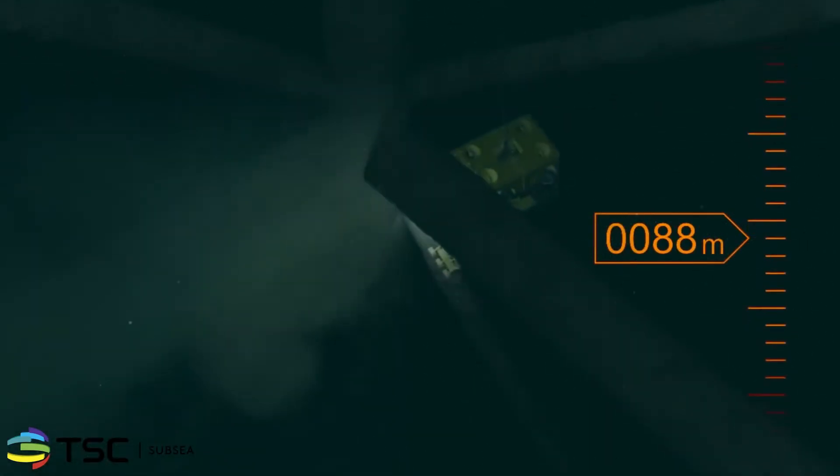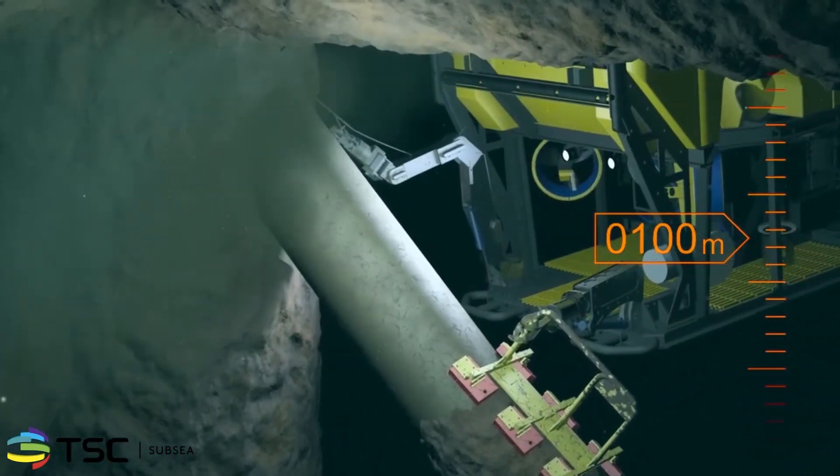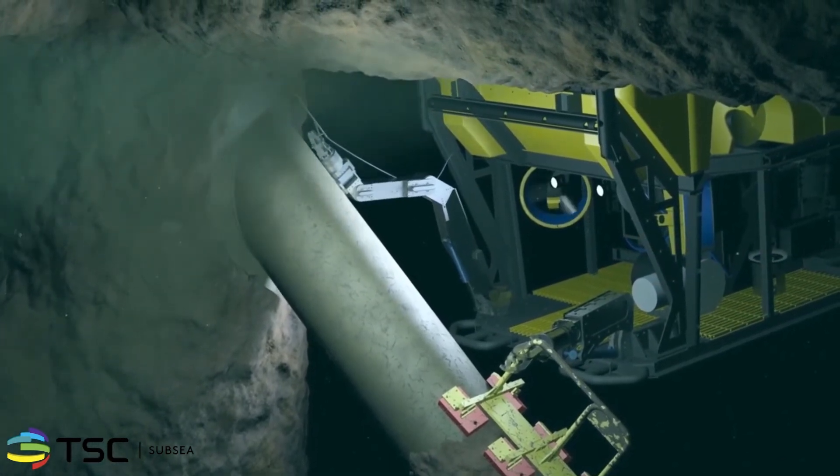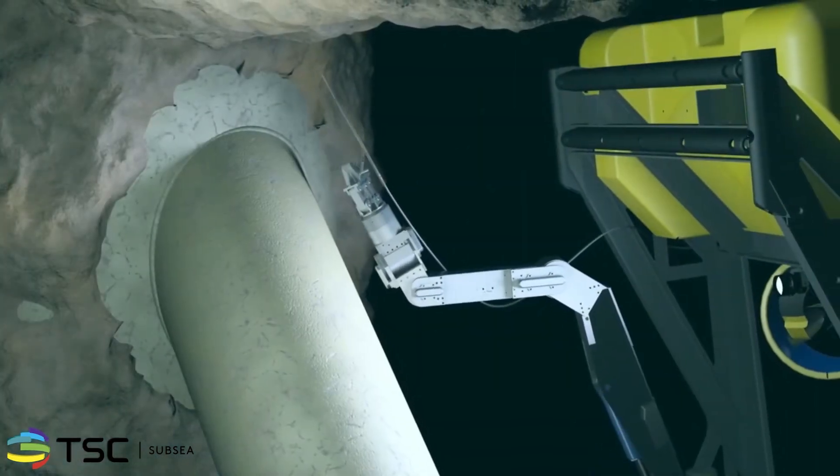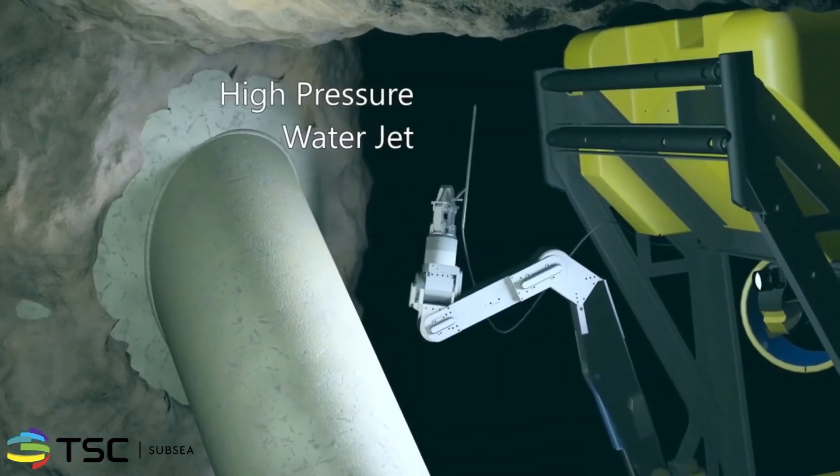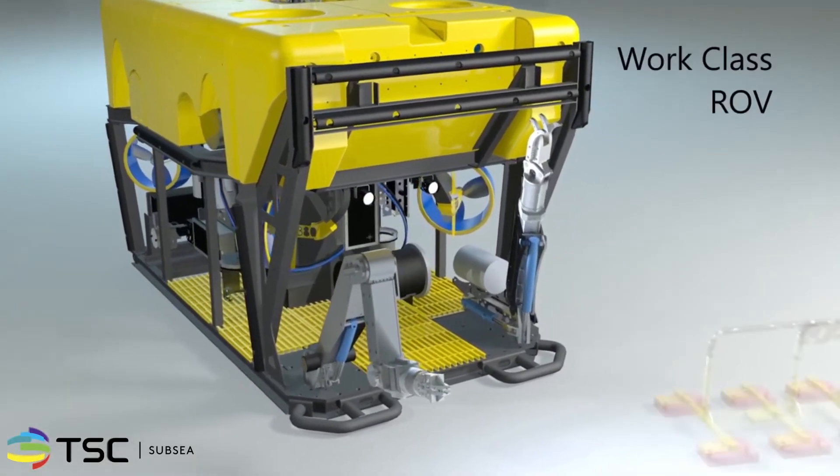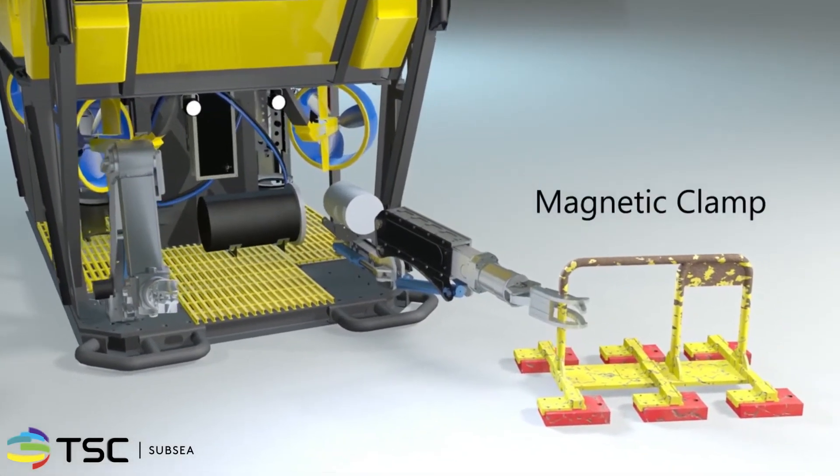In preparation for the inspection, the weld must be cleaned to SA2 standards and the surrounding areas to SA1. Cleaning to SA2.5 levels is not necessary because coatings and residual marine growth do not obstruct the ACFM scanning technique. A variety of cleaning techniques such as a high pressure water jet can be used to perform this task. The tooling for both the cleaning and inspection is delivered from an ROV platform, the stability of which is supported by magnetic clamps that attach to the structure.